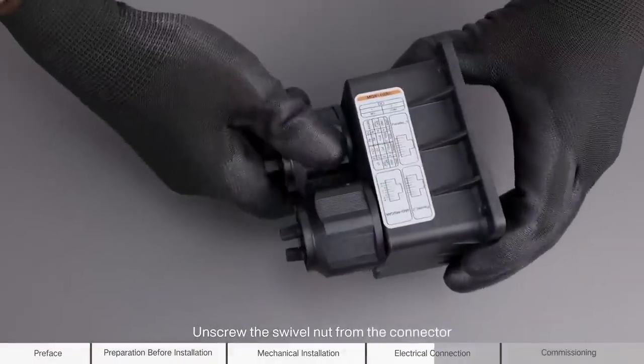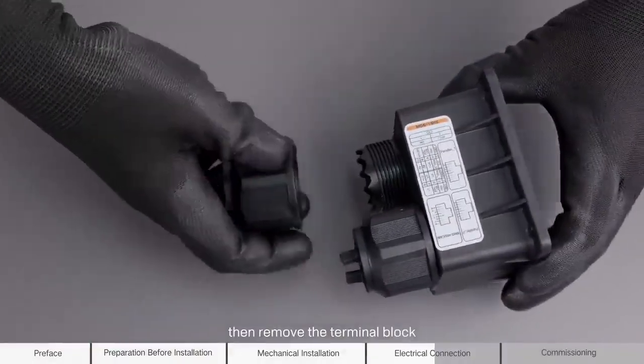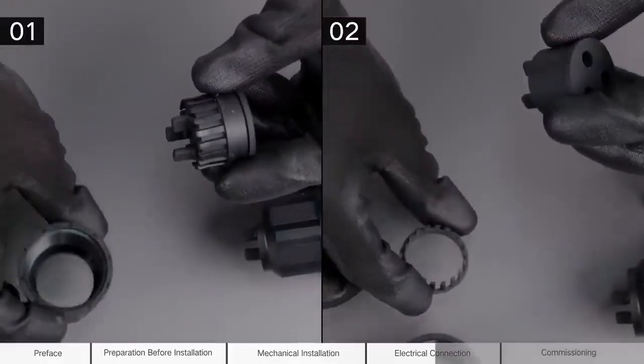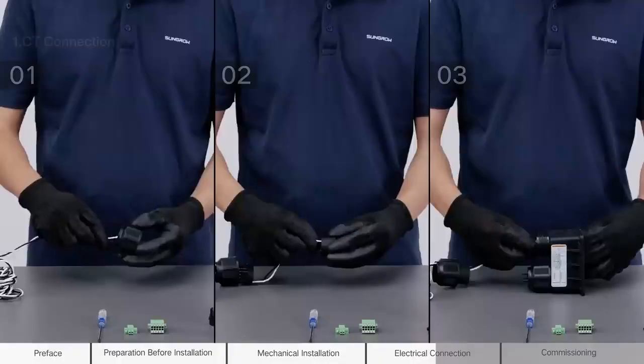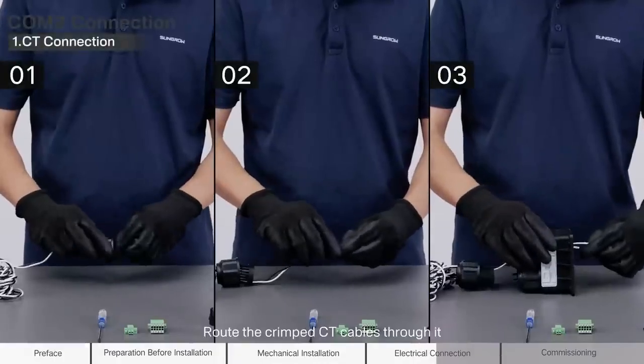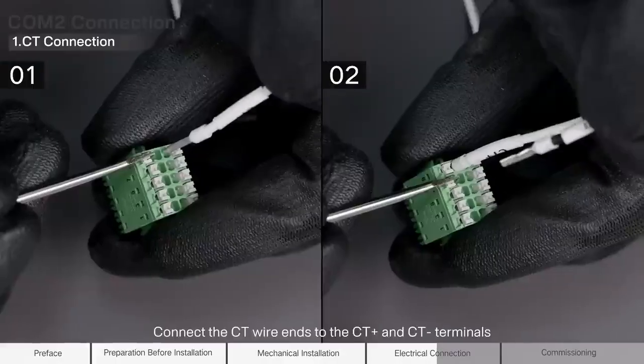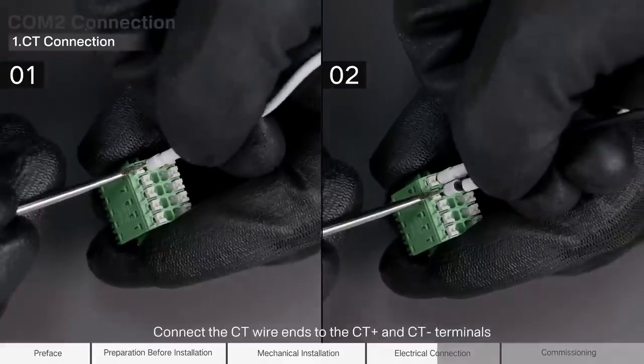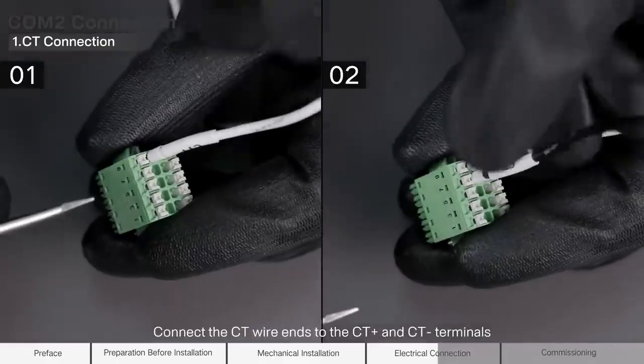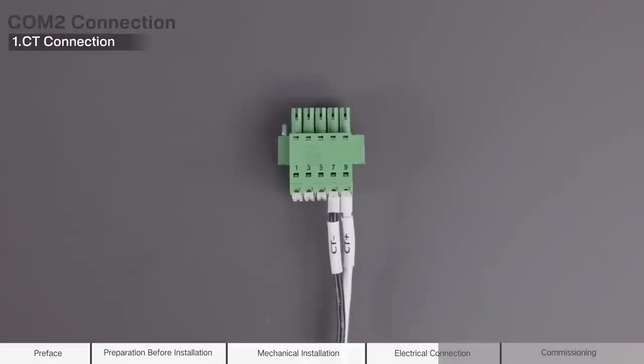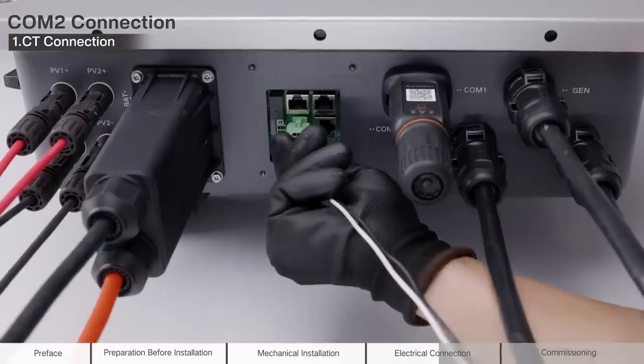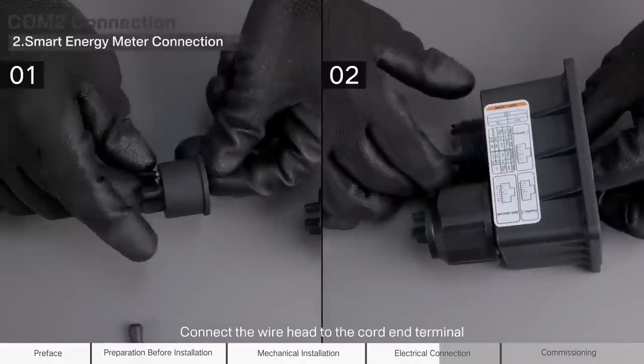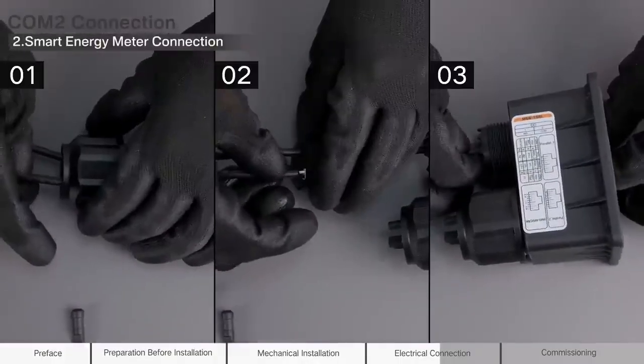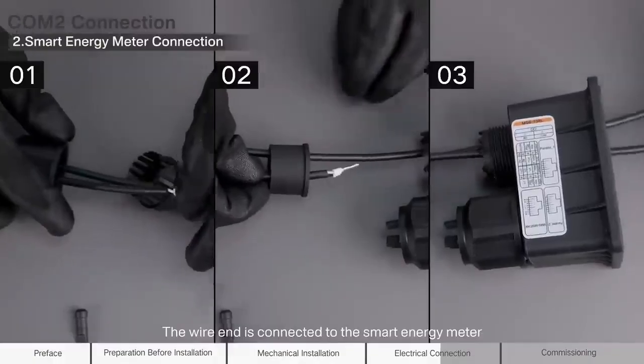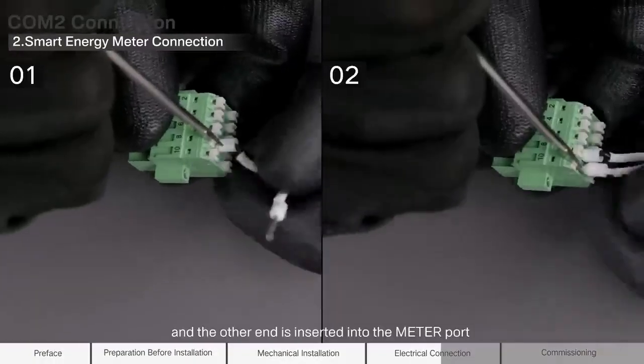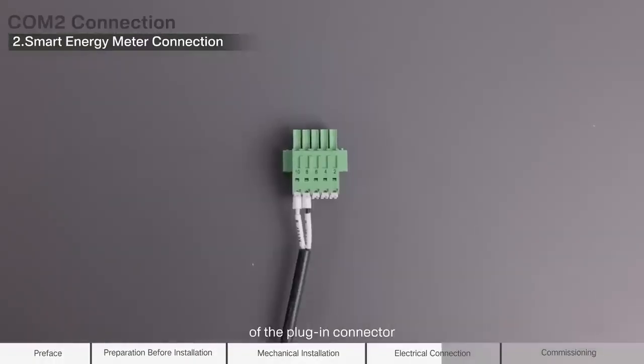Unscrew the swivel nut from the connector, then remove the terminal block. Remove the sealing ring. Route the crimped CT cables through it. Connect the CT wire ends to the CT plus and CT minus terminals on the pluggable connector. Connect the wire head to the cord end terminal. The wire end is connected to the smart energy meter, and the other end is inserted into the meter port of the plug-in connector.